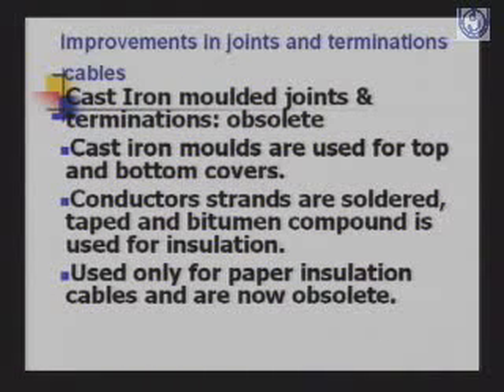In case of cables, improvements in joints and terminations have come up. Earlier we were using cast iron molded joints and terminations, which are now obsolete. Cast iron molds were used for top and bottom covers. Conductor strands are soldered, taped, and bitumen compound is used for insulation. These were used only for paper insulation cables but are now obsolete.